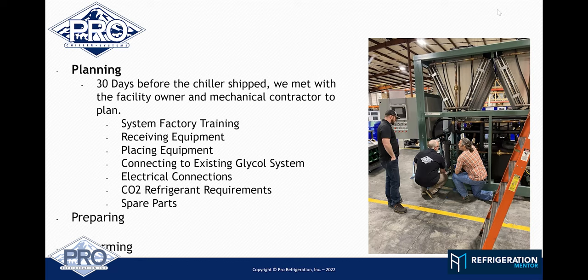You guys design chillers differently than most—you do a full package, right? So it's not just the chiller, you get the whole pump skid and everything with it. You've got your glycol storage reservoir and your fluid delivery pump feeding coolant into the customer's process loop. At its simplest, when it shows up, you hook power into it, fill the reservoir with glycol, make sure your process fluid piping is pressure tested, and then you start turning switches on and you're running.